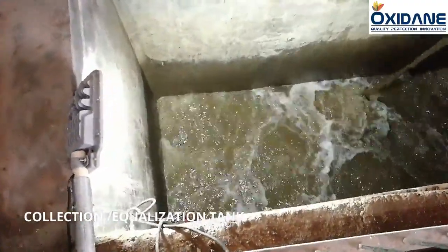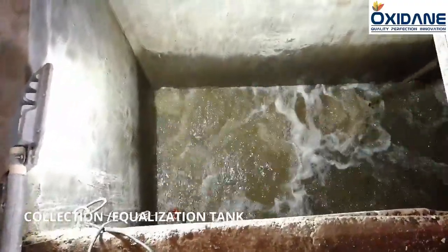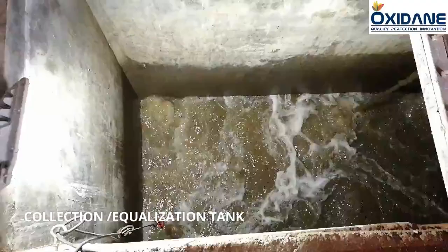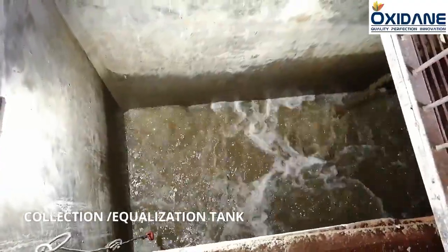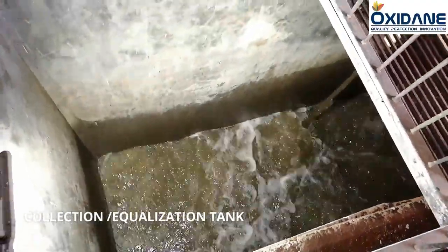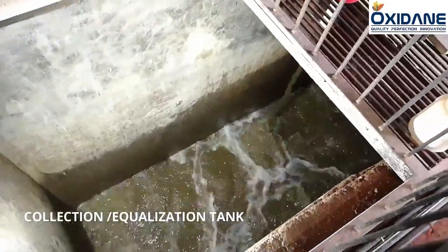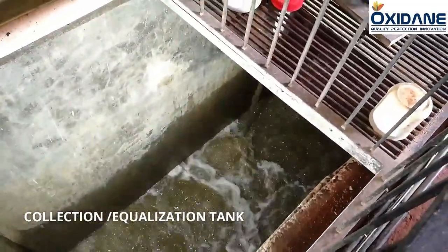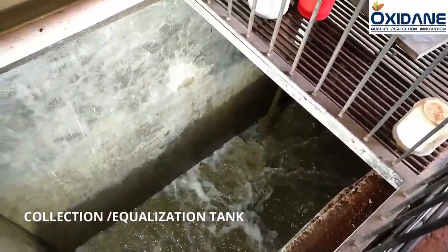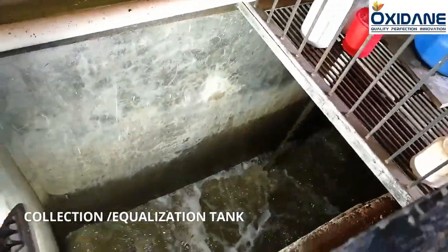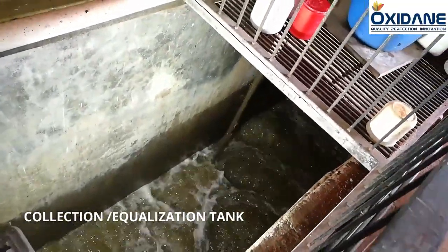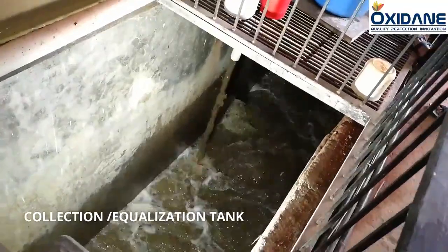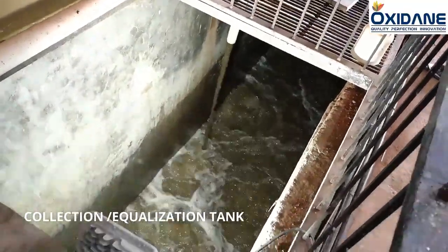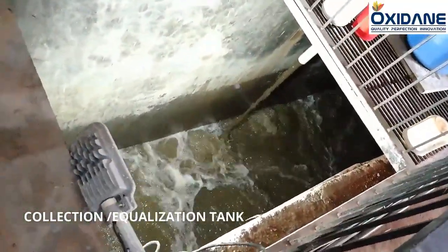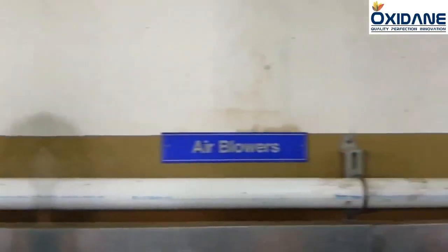During the peak hours, sewage comes at a high rate. The equalization tank stores this sewage, and lets it out during the non-peak time when there is little incoming sewage. The daily flow of sewage varies from peak flow to lean flow, in order to equalize all the characteristics and flow of sewage before it is subjected to treatment. The sewage is collected in the equalization tank, where the solids are kept in suspension by blowing air and avoiding septicity.